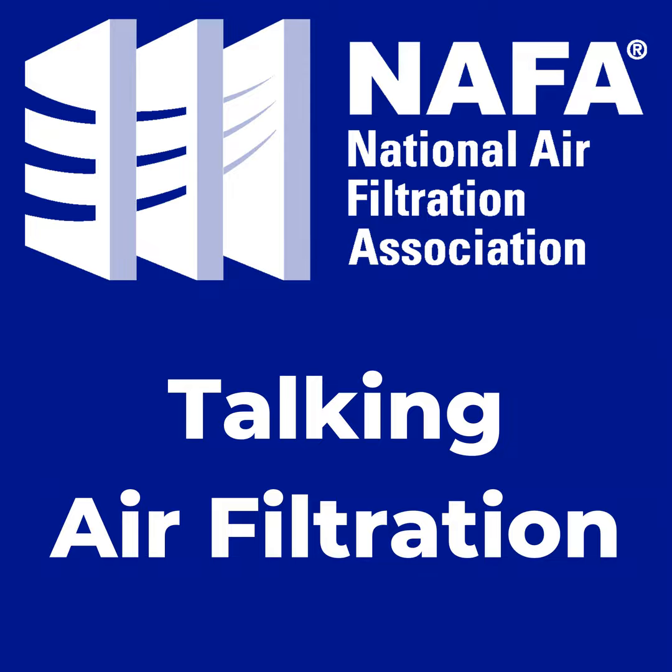And then again, dust load. When you look at the initial resistance and the dust loading capacity, we tried to boost the efficiency of a MERV 8 filter with nanofibers. You can see here we almost doubled the initial resistance, so you're getting better mechanical performance of the filter media, but you're also taking that dust holding capacity and significantly reducing it.